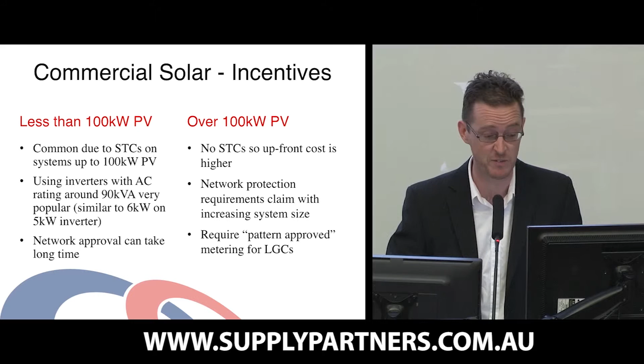Over 100 kilowatts, obviously no STCs, so the upfront cost is higher. Network protection requirements can really climb as well, and that means that you have to use larger and more sophisticated and frankly more expensive network protection relays. And don't forget to put in fully approved monitoring for LGCs. I've heard of installations where this was an afterthought, or it wasn't done correctly, or the LGC monitoring was just not locked down at the time of installation, and 12 months can go past and those LGCs are effectively lost.